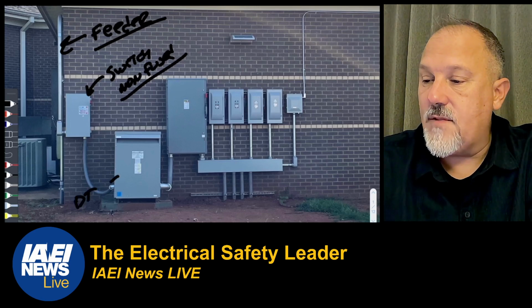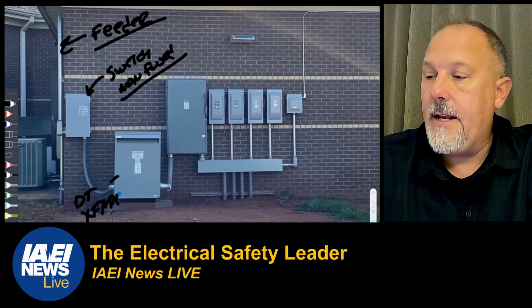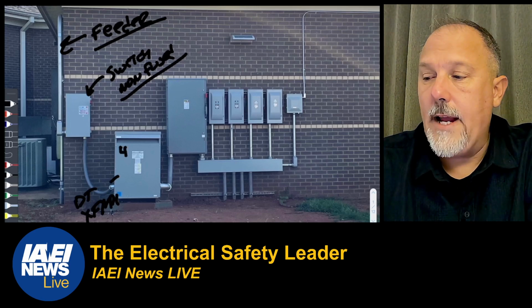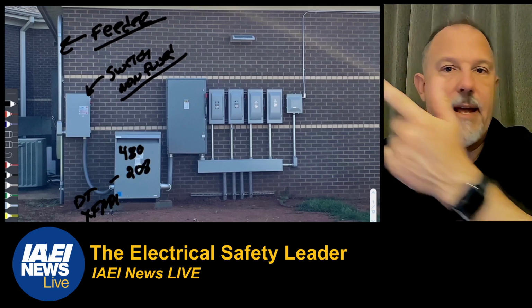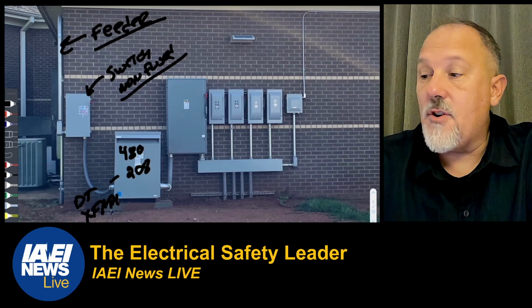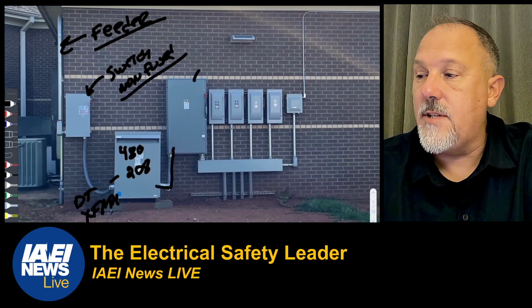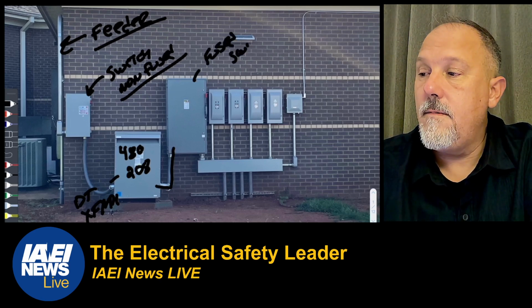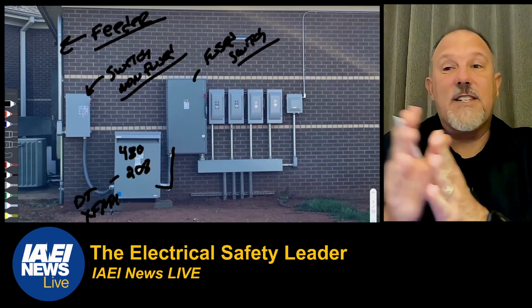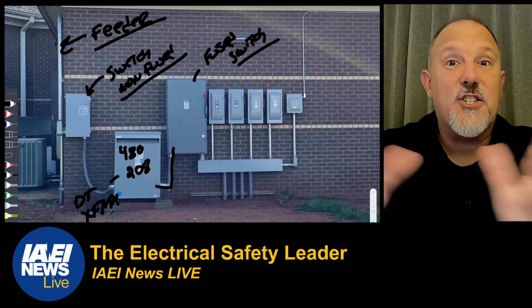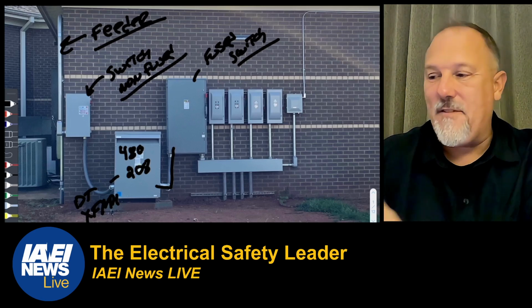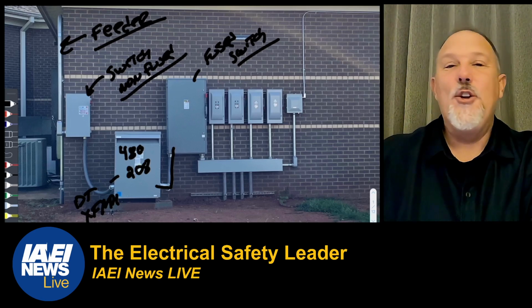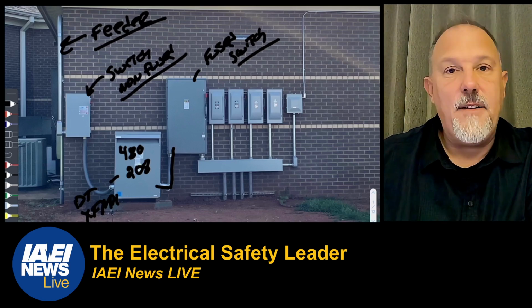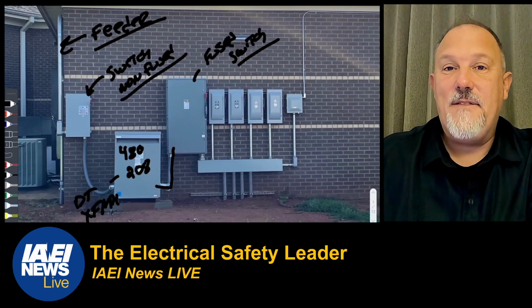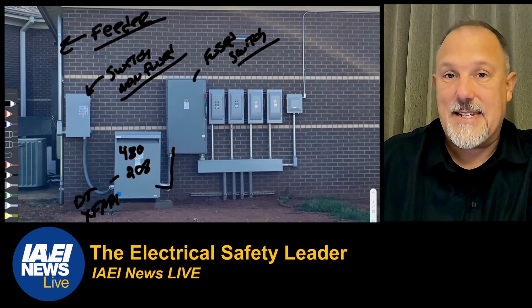This is a dry type transformer, and it is 480 to 208. Okay, and the impedance, I have the impedance on another diagram. So I come through this transformer, I come into a safety disconnect switch. So this is a fused switch, and we have to figure out what size fused switch that we need on there, and that's transformer basics. Okay, so you have a basic transformer. You have to determine the full load amps of the transformer. You have to figure out the size of the transformer secondary conductors, what the overcurrent device is on the secondary, what's that size that you want to put in there.